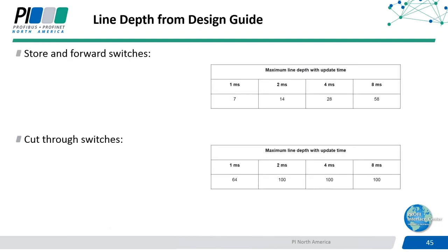So if we look at this table from our design guide, and go back to the example I mentioned earlier, we had configured 64 devices in our engineering tool at 1 millisecond and were going to download to the controller and start it up. It just so happened we had a line topology in this case, and if we were using store-and-forward switches, that wouldn't work because you can only have a maximum of 7 in a line. So we'd probably need some distribution switches, and we'd only be able to go a maximum of 7 hops from the controller to the device. However, if we were using cut-through switches, or IRT which already has it, we'd be okay because we could have 64 devices at 1 millisecond, meaning we could run all those switches through and it would work. So keep in mind, update time and switch type should be investigated when designing the system and looking at the line sections of your topology.